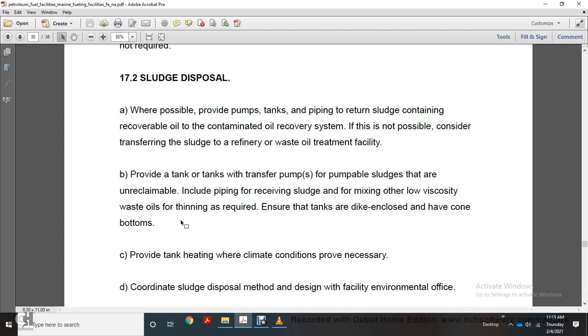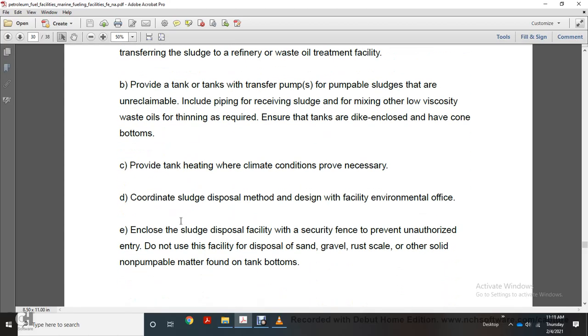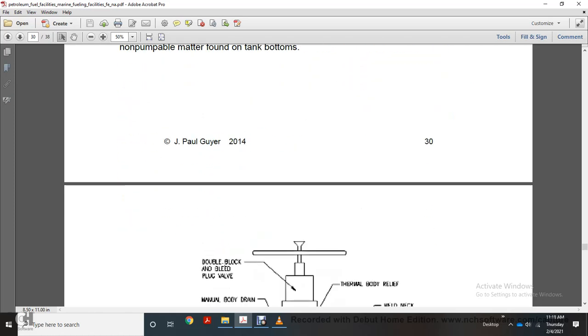Ensure the tanks are diked and enclosed and have cone bottoms. Provide tank heating appropriate to climate conditions if necessary. Determine the sludge disposal method with the facility environmental office. Enclose the sludge disposal facility with a security fence to prevent unauthorized entry. Do not use the facility to dispose of sand, gravel, rust scale, or other solid, non-pumpable matter found on tank bottoms.